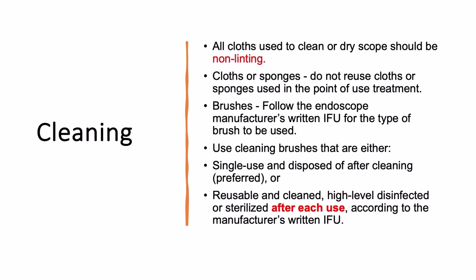When you do cleaning of the scope, all cloths used to clean or dry the scope should be non-linting. Cloths or sponges should not be reused. Brushes, follow the endoscope manufacturer's written instruction for the type of brush to be used. Use cleaning brushes that are either single-use and disposed of after cleaning one scope, which is preferred, or reusable and cleaned, high-level disinfected, or sterilized after each use, according to the manufacturer's written instructions. So those are your two choices.